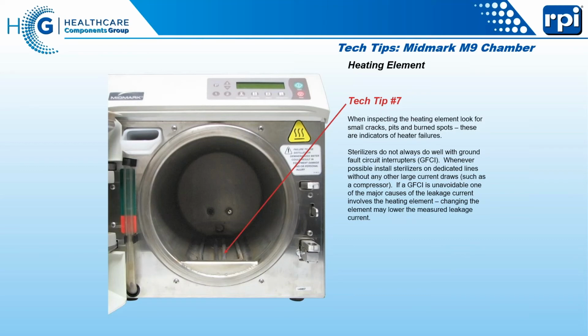If you do want to look at the machine to this detail, take a look at the heating element down there. I have seen a failed heating element. It is the ugliest thing you've ever seen. You don't want to have it happen. So if you do see pitting or what look like cracks starting to develop in that heating element, before it fails, please replace it. You don't want to have to go through cleaning the material and that heating element out of every single spot in the sterilizer. It's ugly.